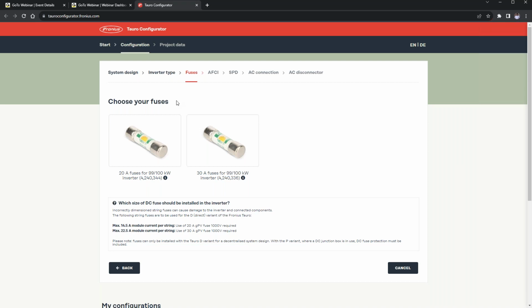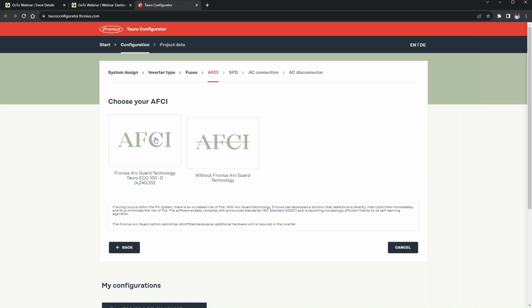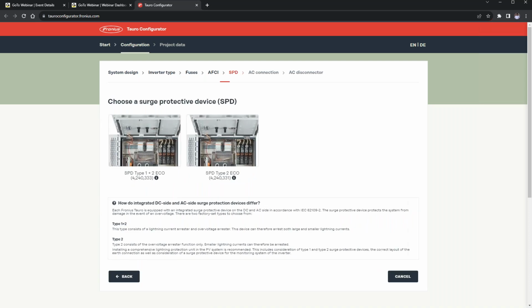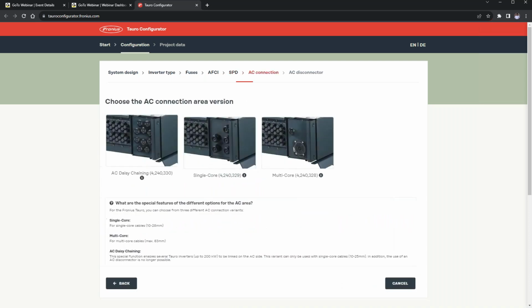So let's say in this case now, we can see that we have the option of selecting fuses. You can go for either the 20 amp fuse or the 30 amp fuse. And if you need more information, please click on the information icon to give you more details about the fuse rating to make use of. In this case, we also have the option of selecting arc fault circuit interruption or not. So let's say we decide to go for the arc fault, and then arc fault protection and then type 1+2 SPD.